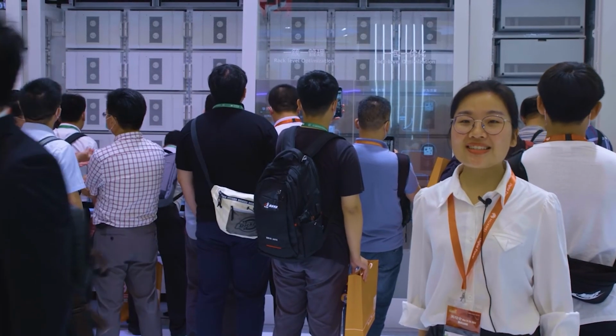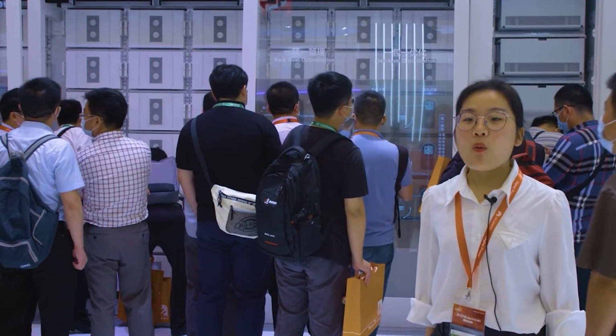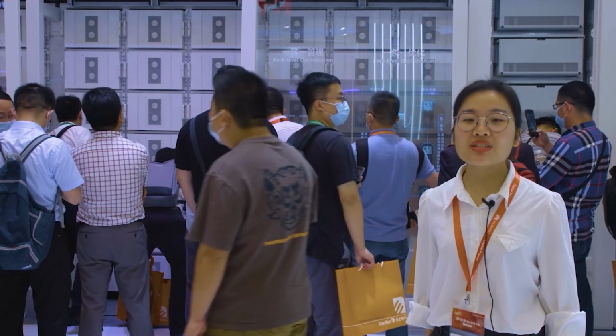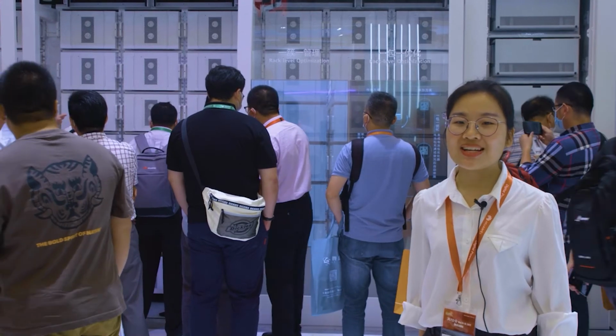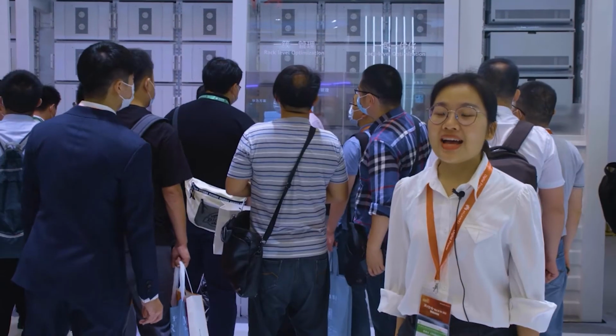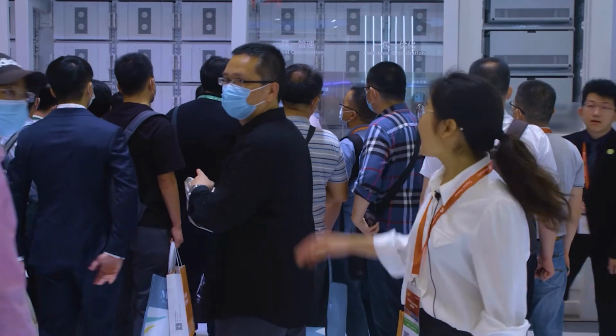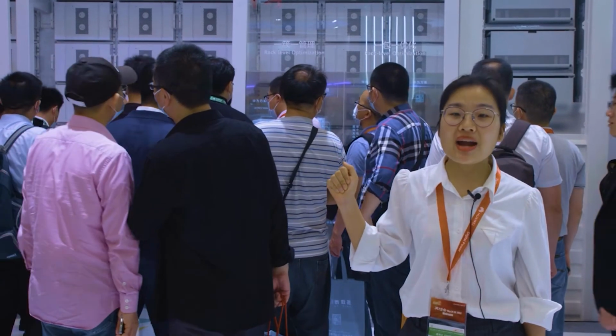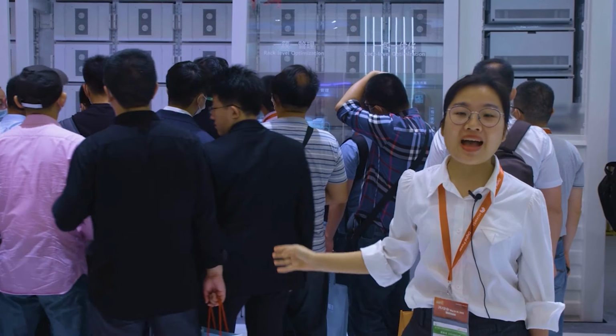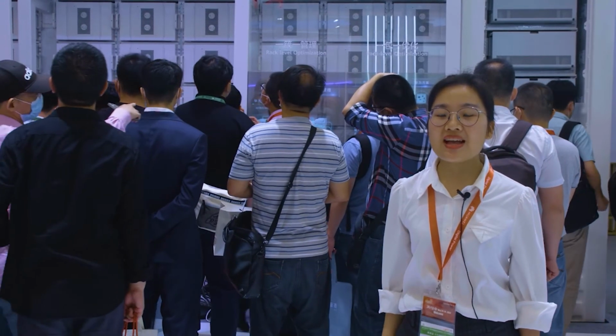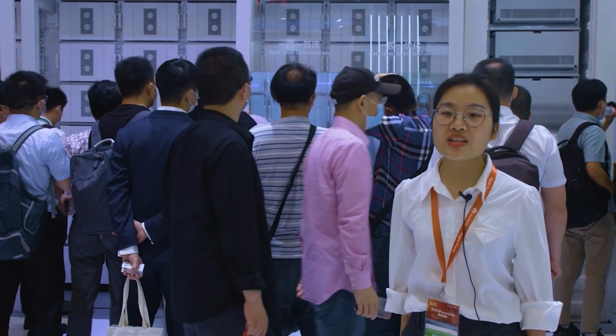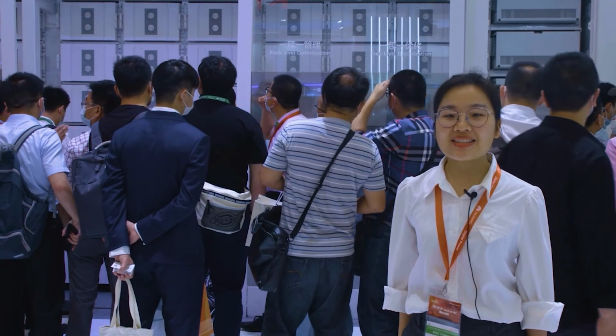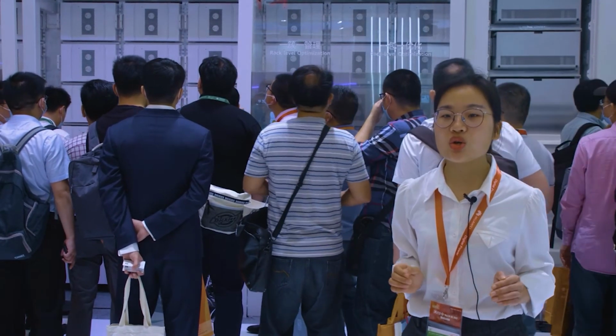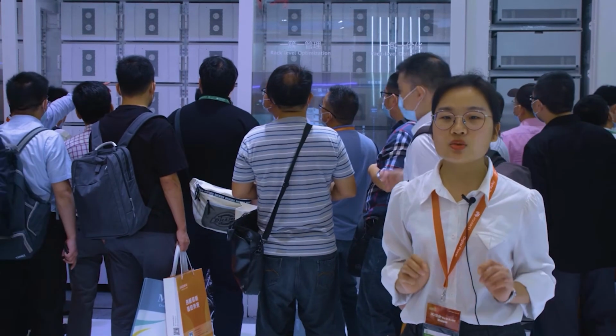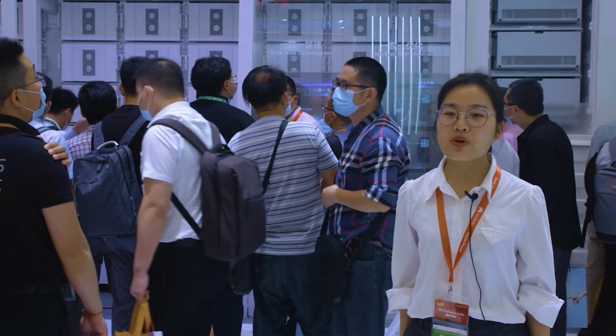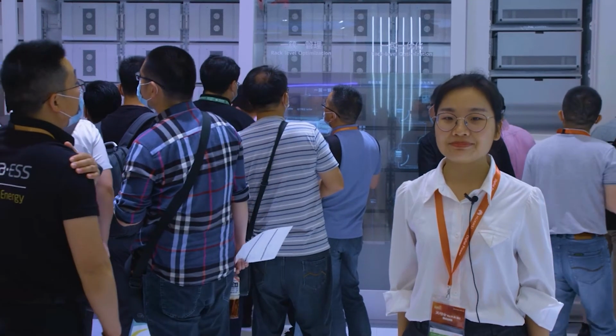Smart String ESS is a standard 20-foot container with rated capacity of 2,064 kWh, a very high power density. As we can see, 6 battery racks are connected in parallel. Each rack has 21 battery packs in series. Each battery pack is 16.384 kWh. Each rack is connected with one DC-DC module, then paralleled into DC bus, and energy is separated into individual PCS.